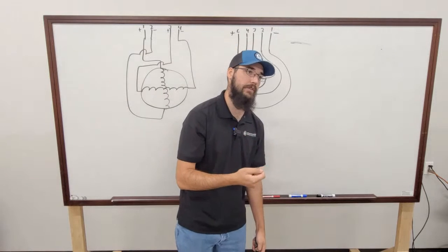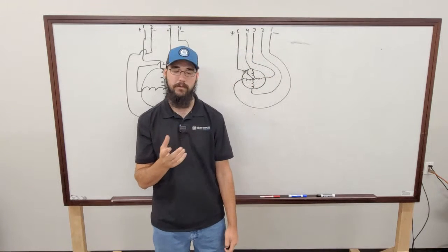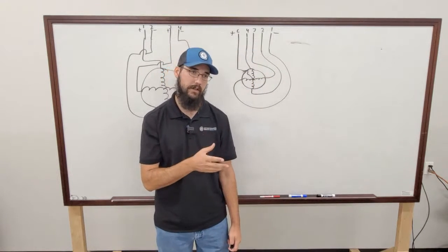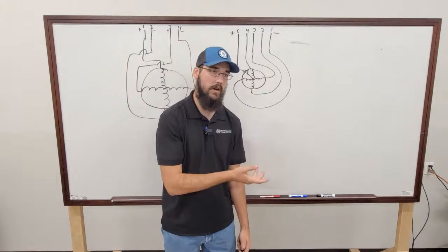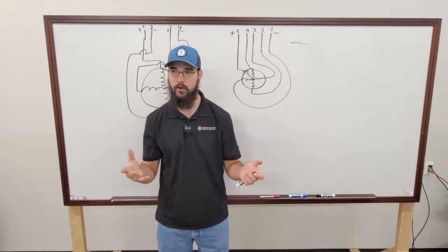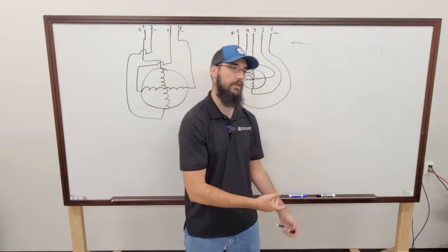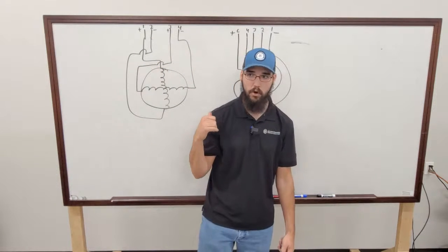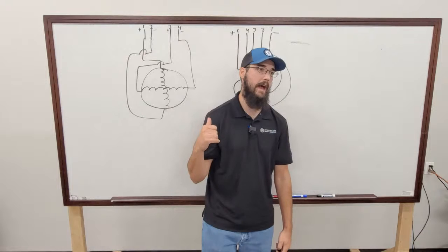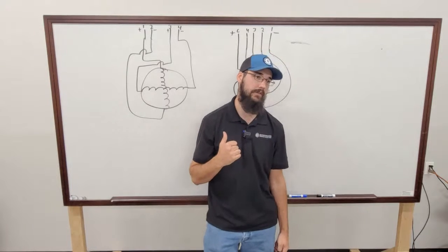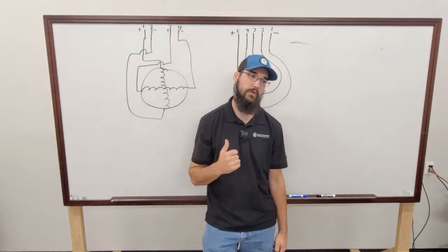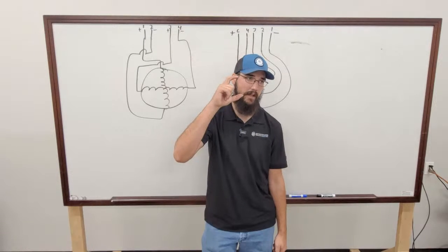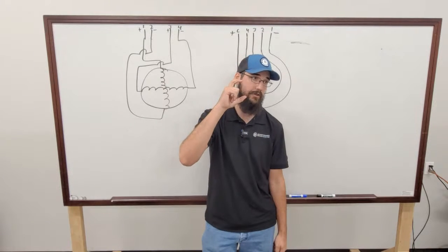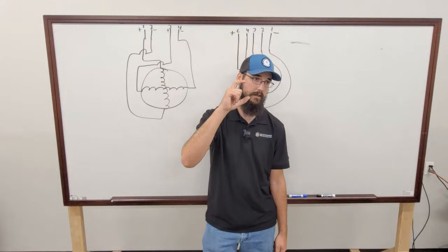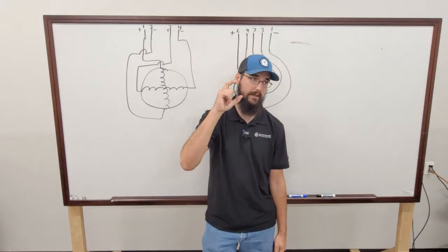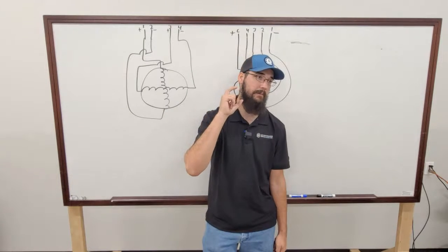Majority of EXVs have a sight glass on them once you get to this large of a scale. Now, smaller systems may not, but most of your chiller systems are going to have some kind of sight glass on the EXV. That sight glass is so that you can watch that plunger actuate. So utilize that to your benefit to try to verify it mechanically.